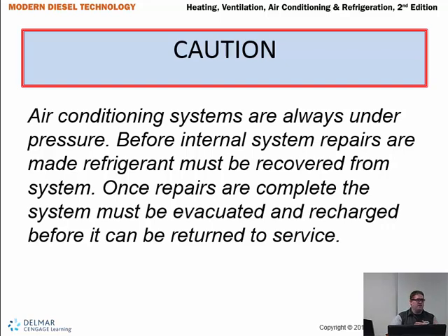Remember, even if the customer comes in and says, I don't have any AC, my uncle drained it or opened it up to atmosphere, assume that some pressure may build in there: residual refrigerant in the desiccant that can leak out, air that can build up pressure inside the system. Don't assume that there's not going to be some pressure in there.